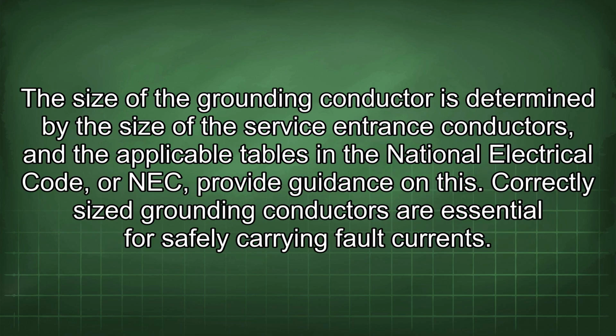The size of the grounding conductor is determined by the size of the service entrance conductors, and the applicable tables in the National Electrical Code, or NEC, provide guidance on this. Correctly sized grounding conductors are essential for safely carrying fault currents.